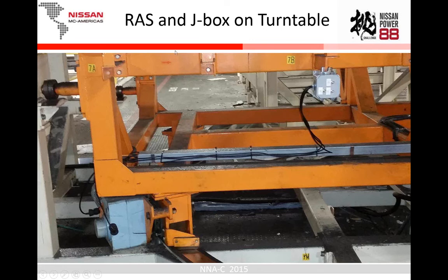Here is one that's a turntable. One trick we've learned is that these cables do not work too well inside of cable tray or cat track. If you have flexible cable tray or cat track, these cables tend to grip other wires and cables that might be in there, and as it's moving, the cables pull, and they'll pull loose from the RAS sensors, or break the RAS sensors off of a gearbox or motor, to where you'll have to go back and repair it.